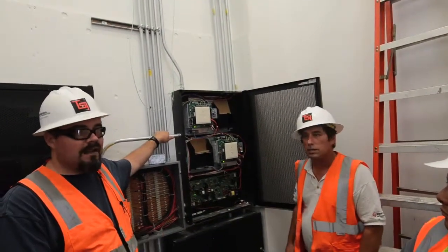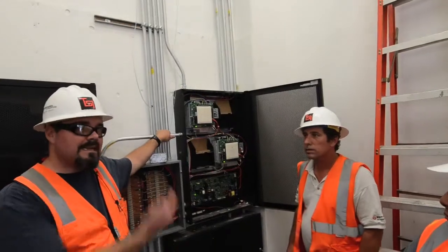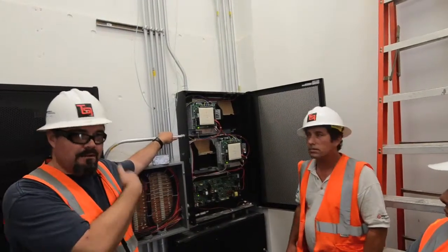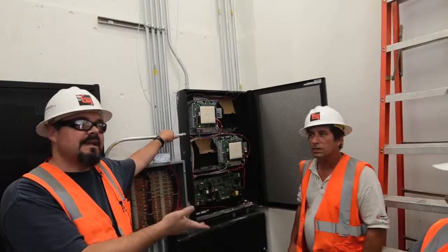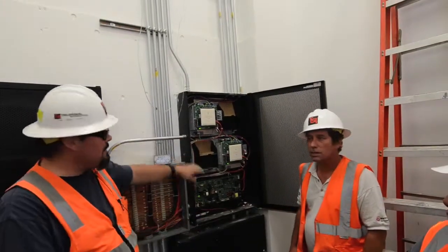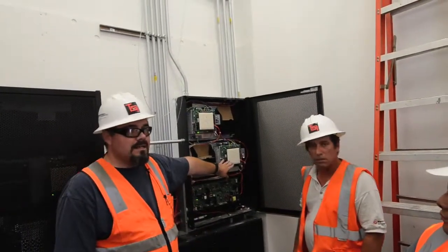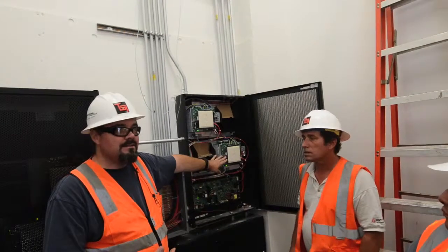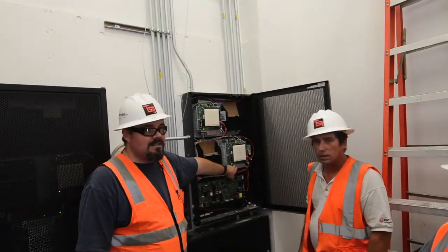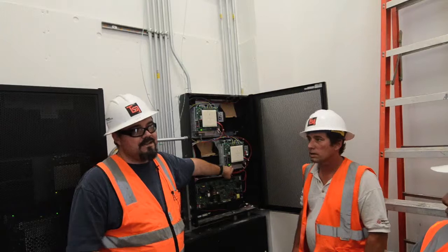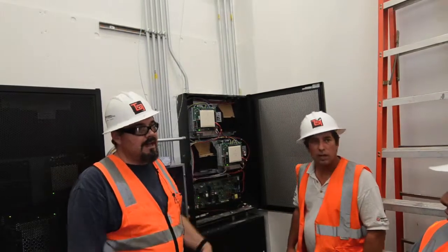But what I did is I installed some new strobes in this morning in those bathrooms. So we had to cut the circuit and we put them in. So it saw no end of line, and it just kept the memory of it being broken. So that's a good indication too. If you come down here and have an issue, you can see if it's blinking or not. Solid means there's still a problem. If it's blinking, it means it was fixed, but it's just remembering that it was broken at one time.